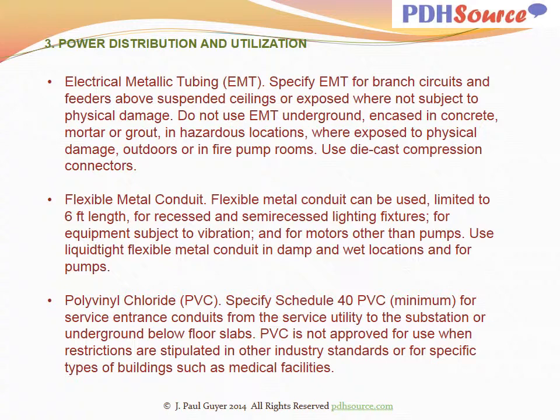Polyvinyl chloride, PVC: specify schedule 40 PVC minimum for service entrance conduits from the service utility to the substation or underground below floor slabs. PVC is not approved for use when restrictions are stipulated in other industry standards or UFCs for specific types of buildings such as medical facilities.